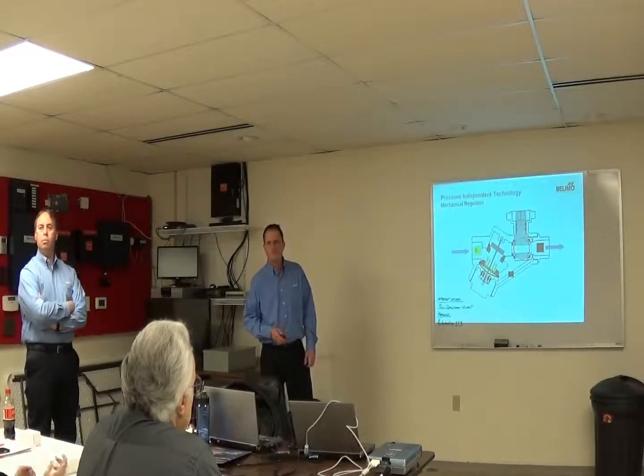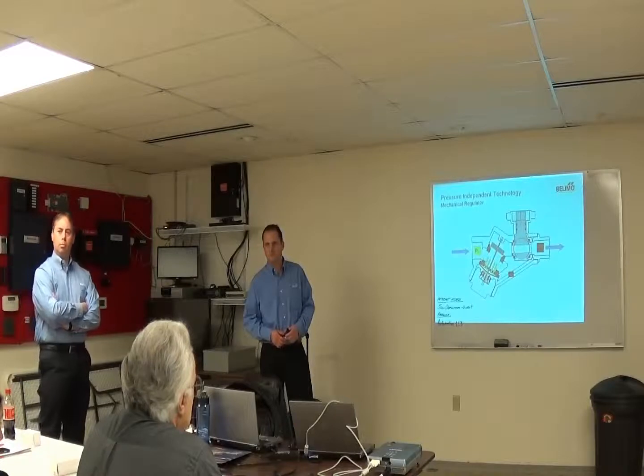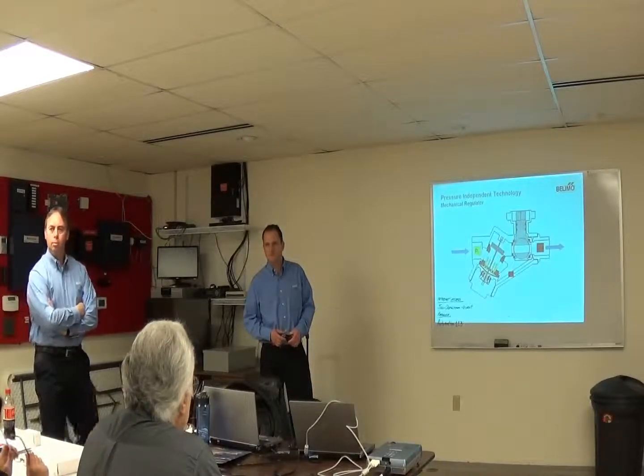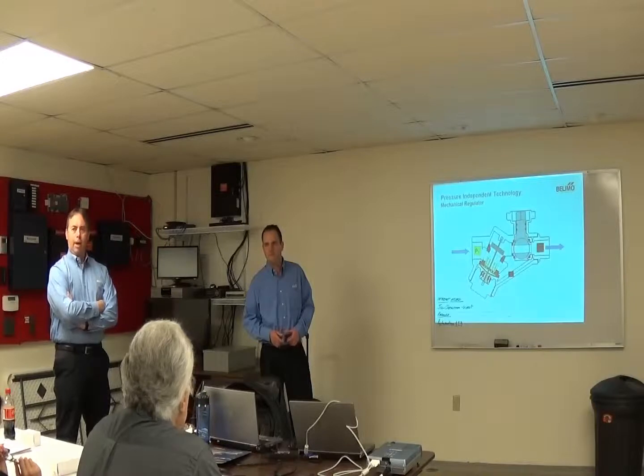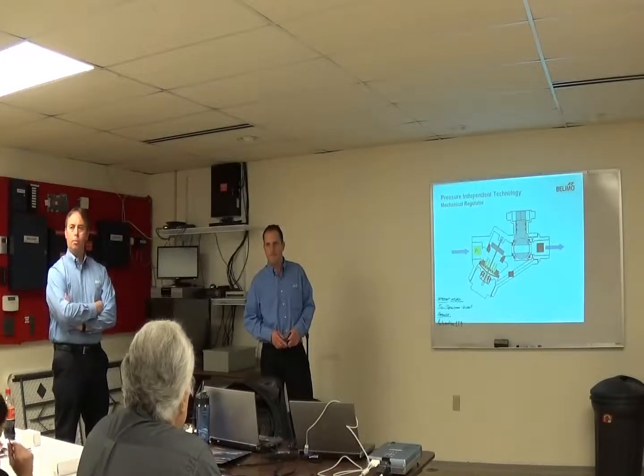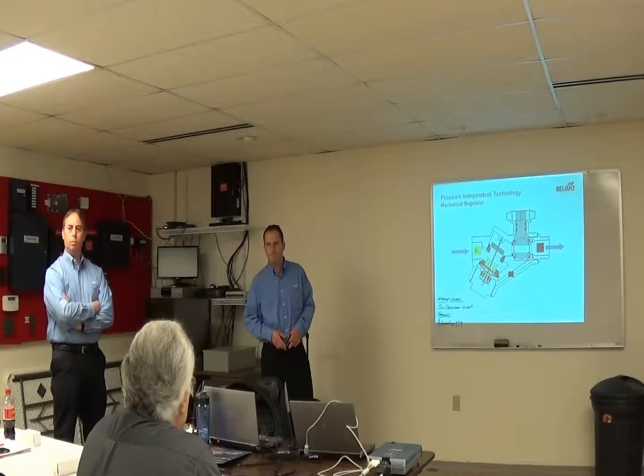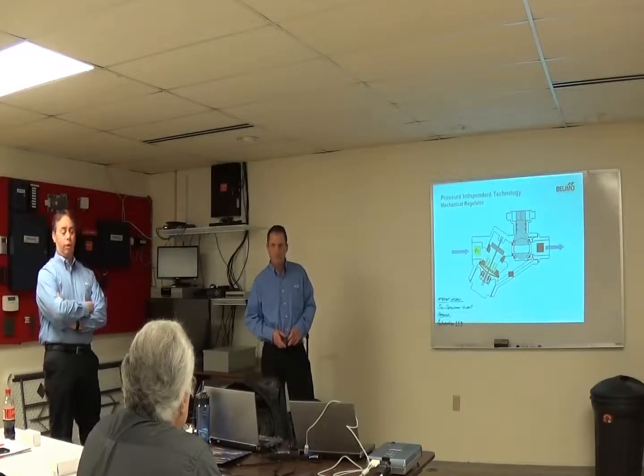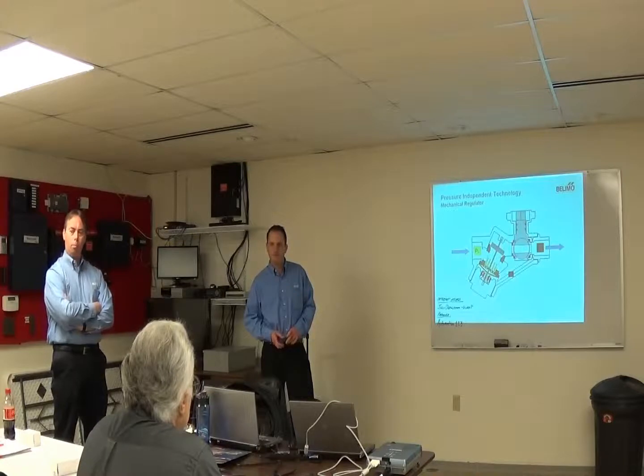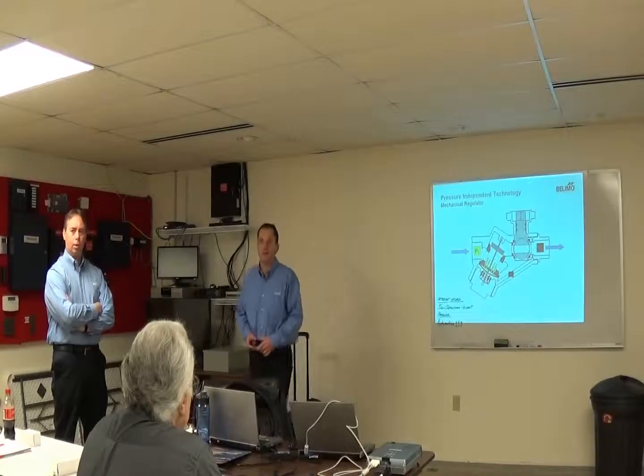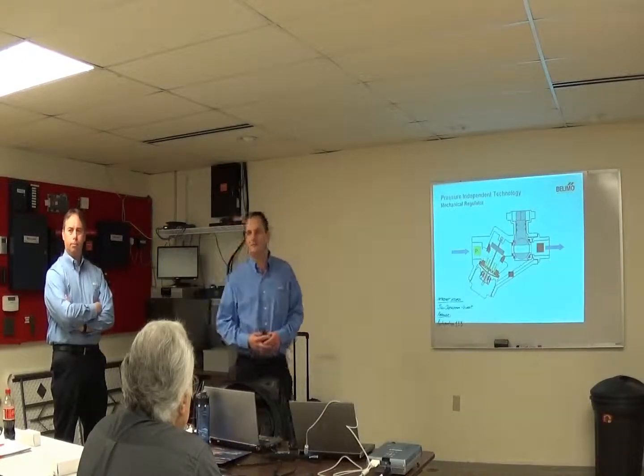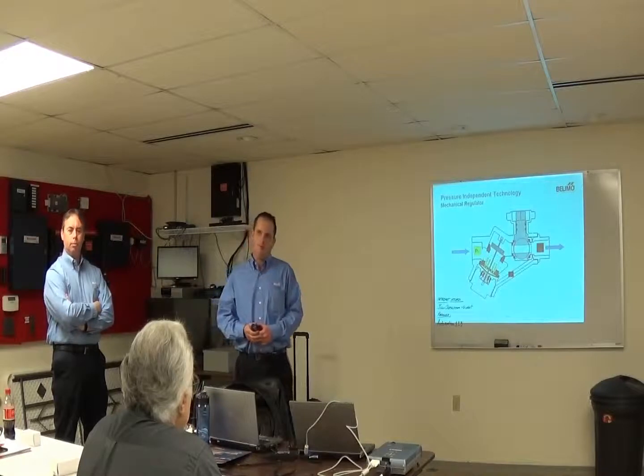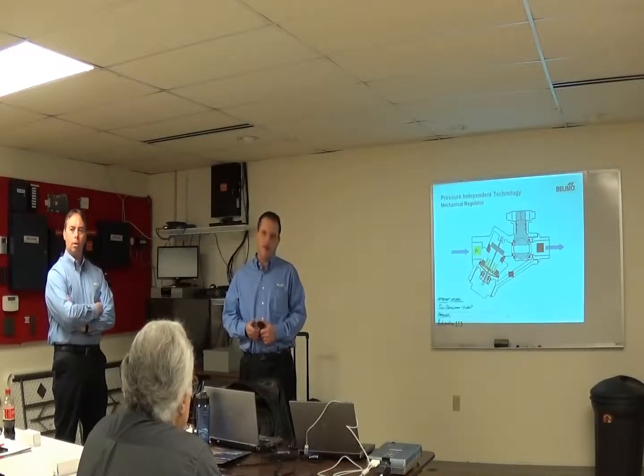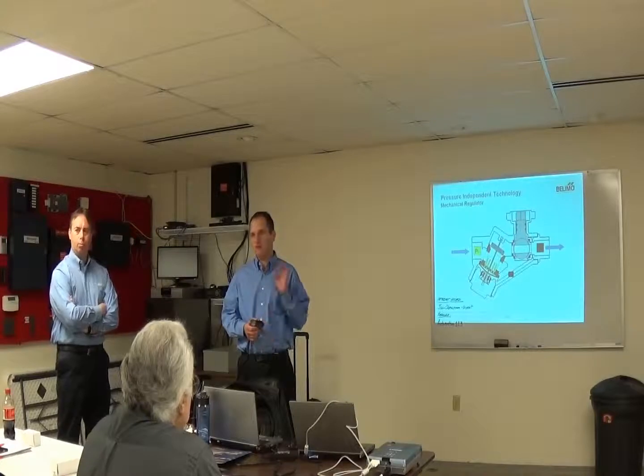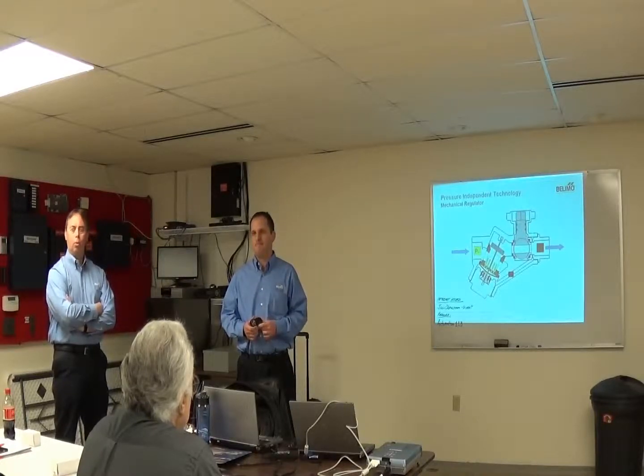On the flow sensors, you mentioned they're ultrasonic on the small ones, and what was it on the larger one? Magnetic. Are straight pipe diameters upstream and downstream required? If you get a cramped mechanical room, are these still applicable? Yep, 5 pipe diameters on the inlet. No requirement on the outlet. Okay, so you have to have at least 5 straight pipe diameters on the inlet. The size of the valve, not the line size. So if you've got a 1/2-inch valve. Yes, pipe diameters, right, the valve size. Correct.